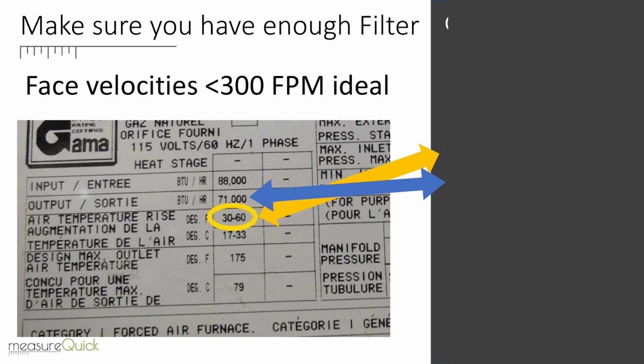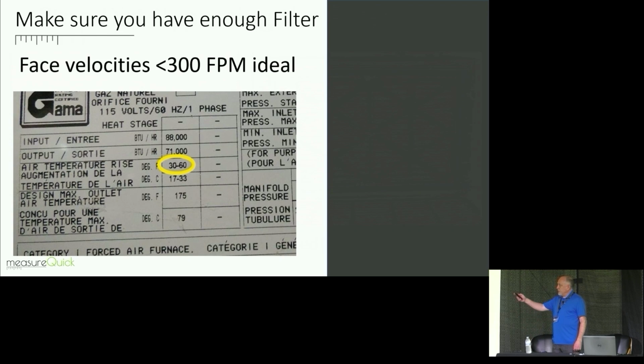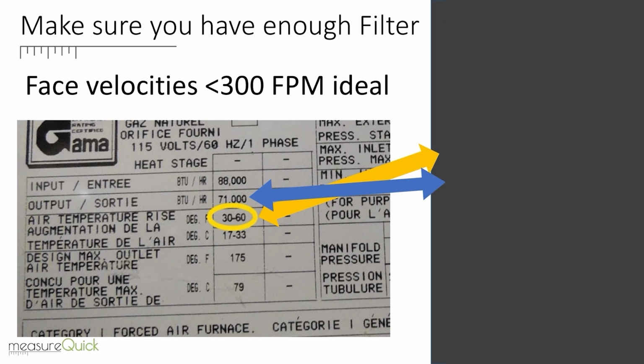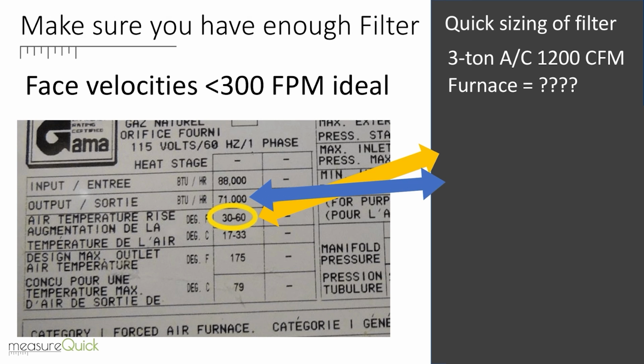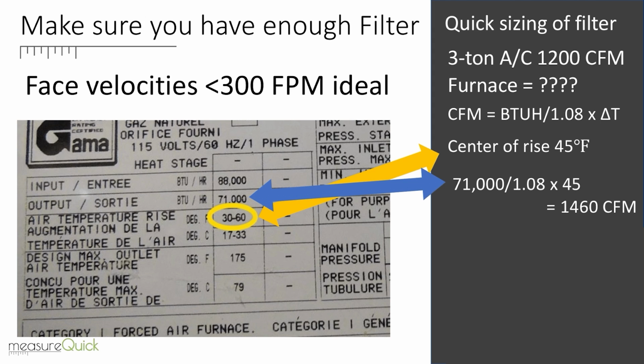This is one I missed for years, was undersized filters on equipment. A lot of times we look at, it's true, air temperature rise 30 to 60 degrees on a furnace, right? 30 to 60 degrees on a furnace. So quick sizing of that, like let's say we had a 3-ton air conditioner. You'd go, okay, well, 3-ton air conditioner, we calculate our CFM. Center of the rise here would be a 45-degree center of the rise. So 71,000 BTU output divided by 1.08 times 45 would tell you, well, you would need about 1,460 CFM for our heating side of the appliance.